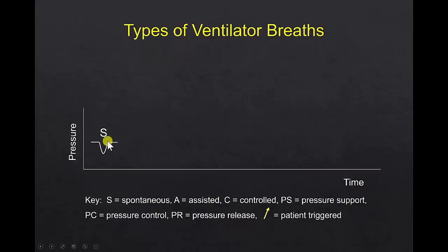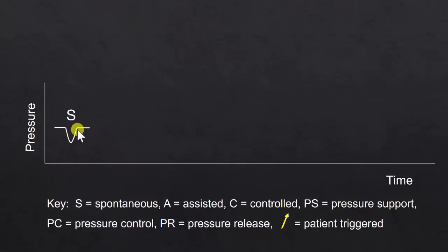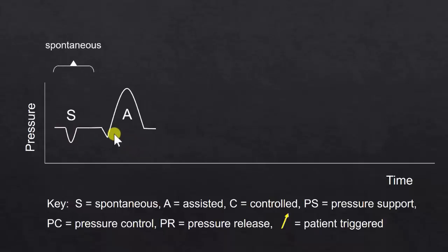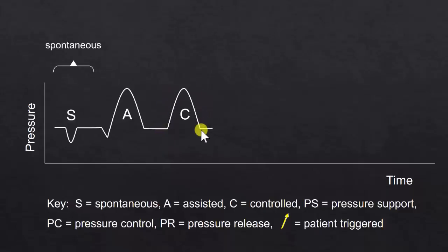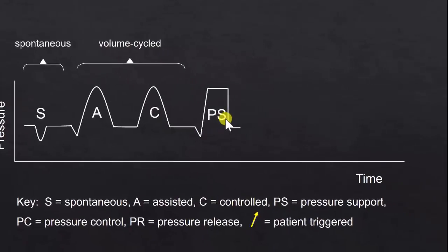Types of ventilator breaths include a spontaneous breath, where the patient breathes through the ventilator circuit — this is a negative pressure breath. There are two types of volume-assisted breaths: an assisted breath, where the patient initiates the breath and once recognized the machine delivers a tidal volume, or a controlled breath, where a timer delivers a tidal volume at a set timing interval. These are called volume-cycled breaths. There are also pressure-cycled breaths — a pressure support breath is where the patient initiates the breath and the ventilator maintains the breath at a target pressure for the duration of the patient's effort.